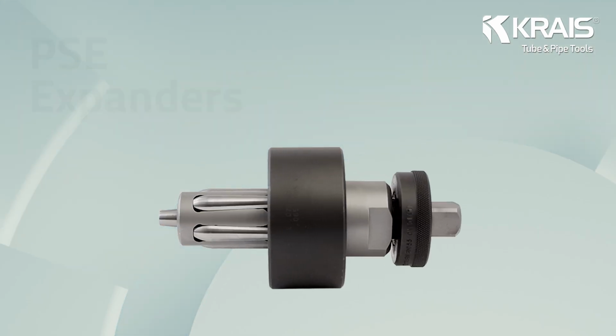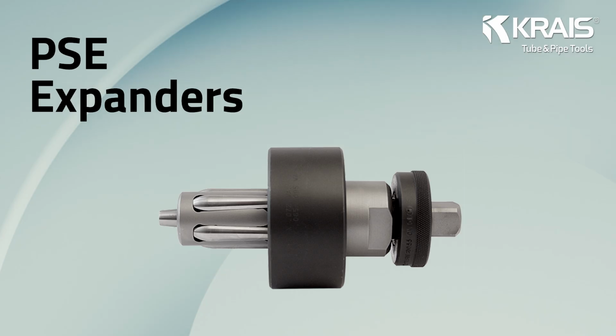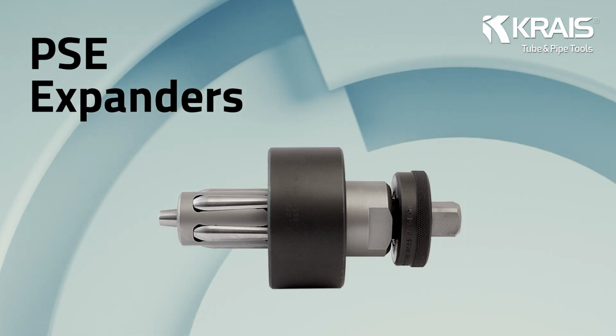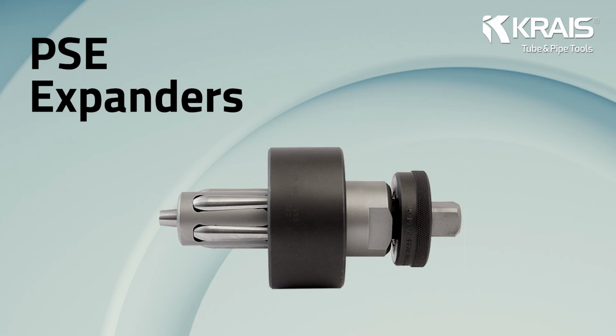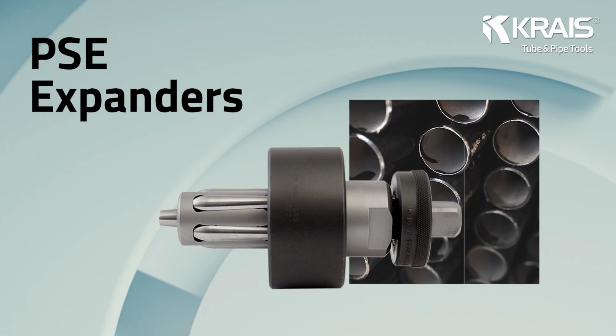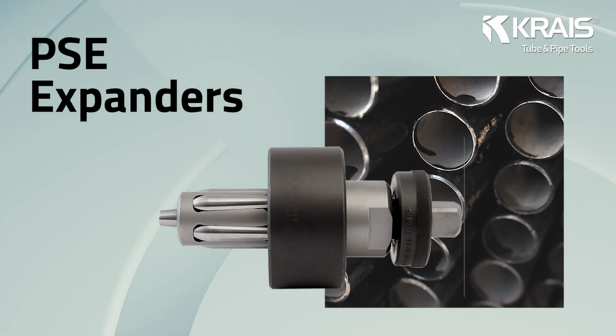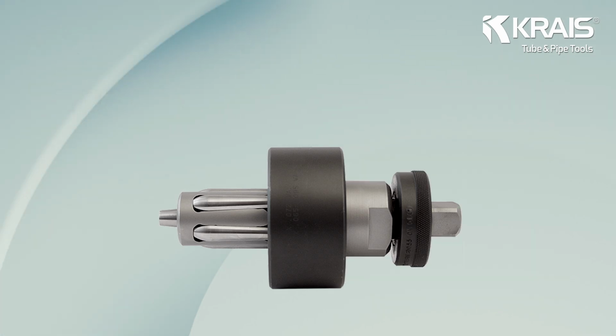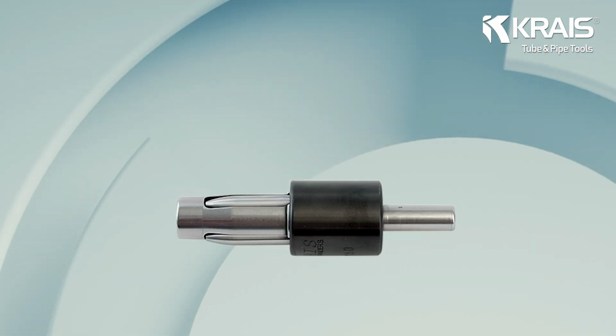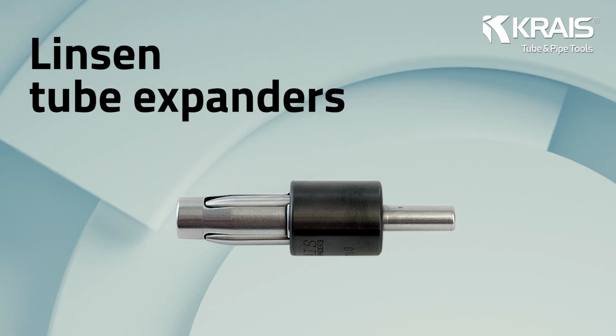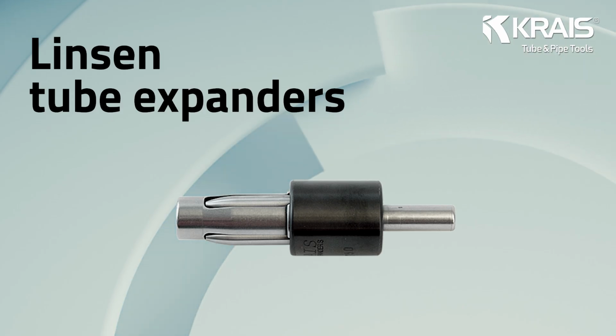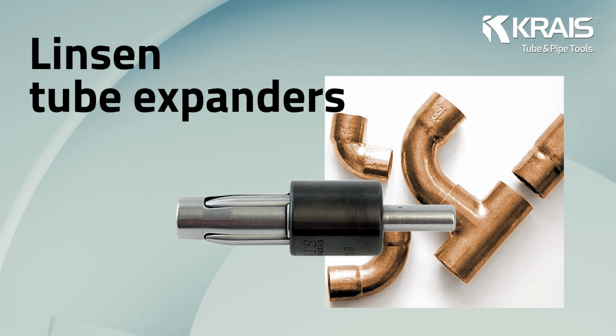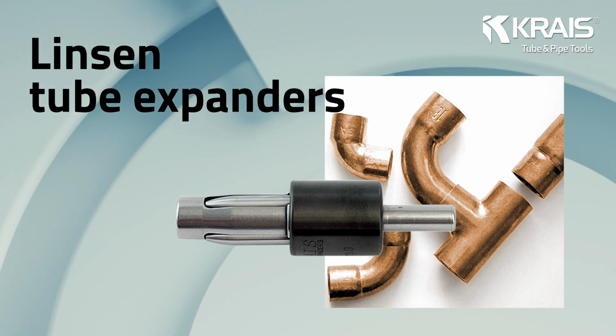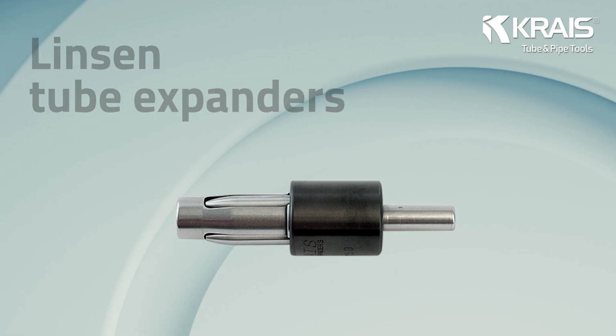KRAIS PSE is used for sizing, calibrating, and expanding pipe ends to achieve correct fit for brazing or slip joint assembly. Maximum capacity is up to 8-inch OD, while the minimum depends on the selected tool version. Linsen expanders are used to expand a tube end so another tube of the same OD can be inserted and brazed, without a separate fitting. This approach is common in refrigeration and HVAC, especially where space is limited and simplified tube-to-tube joints are preferred.